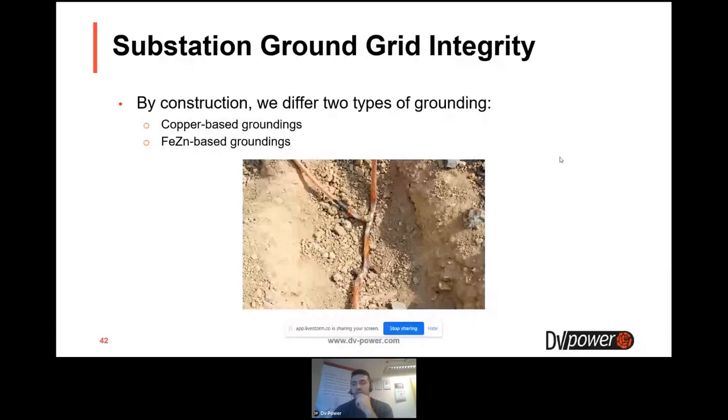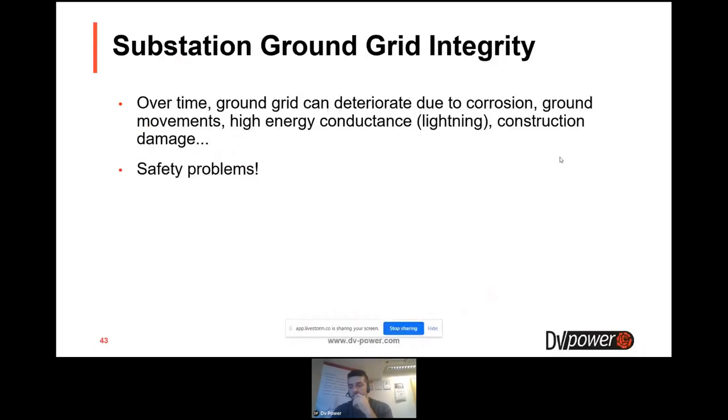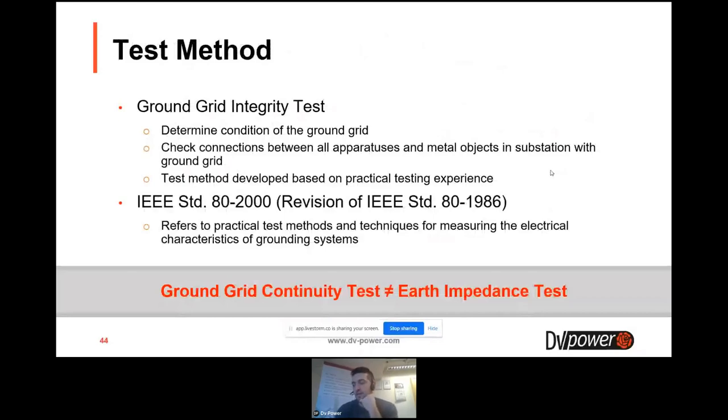not testing soil resistivity, but, how to say, the conductivity of the metal parts which are installed below the substation. And this metal grid below the substation can be damaged due to different factors. From the USA we got the interesting information that these earthing conductors were stolen from some substations, although it's very hard to dig it from the ground, but there is also a similar situation where these ground grids are damaged in this way.